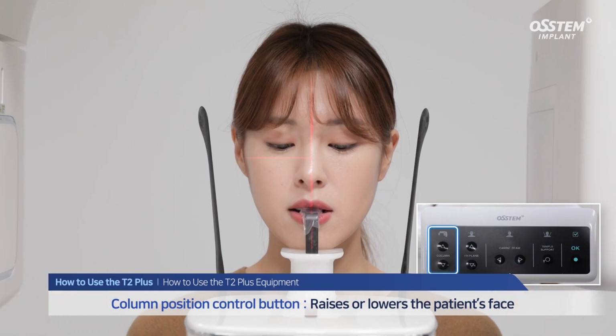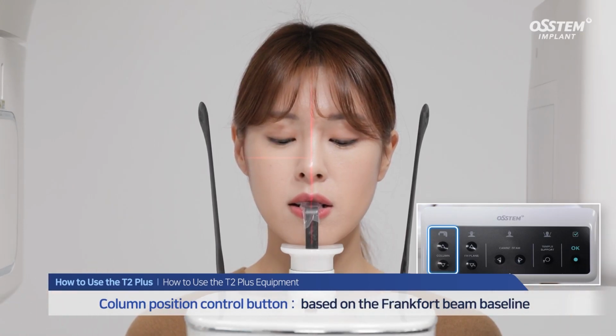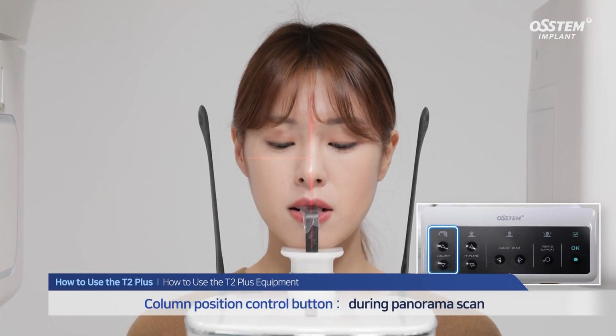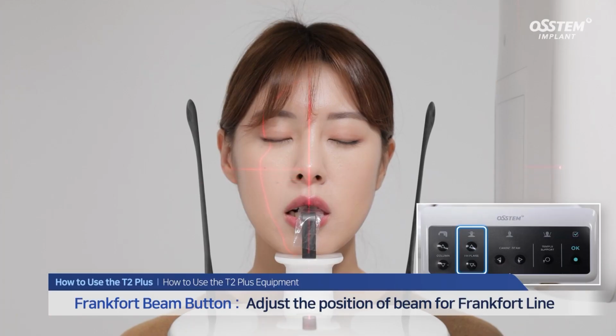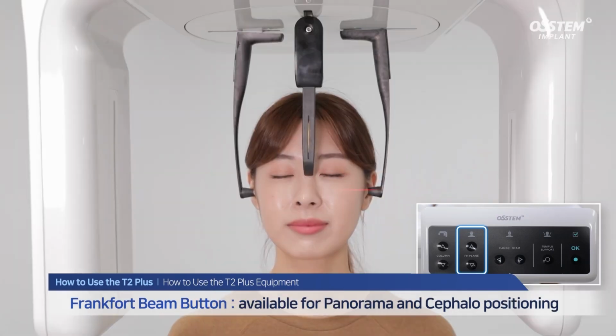During a panorama scan, adjust the Frankfurt beam to the baseline under the eyes. Then, raise or lower the patient's face using the column button. Frankfurt beam button. Adjust the position of the beam to the Frankfurt line, which is the baseline for the patient scanning. This is mainly used for panorama and cephalo positioning.